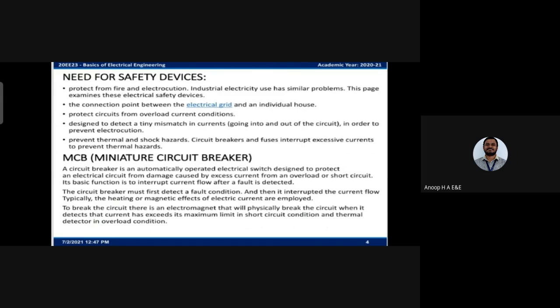Needs for safety devices. The needs are very important because they protect us from fire and prevent electrocution. They protect the circuit from overload current conditions. They detect mismatches in current and prevent thermal and shock hazards. MCB, known as miniature circuit breaker, is an automatically operated electrical switch designed to protect an electrical circuit from damage caused by excess current from an overload. To break the circuit, an electromagnet physically breaks the circuit when it detects that the current exceeds its limit in a short circuit condition.